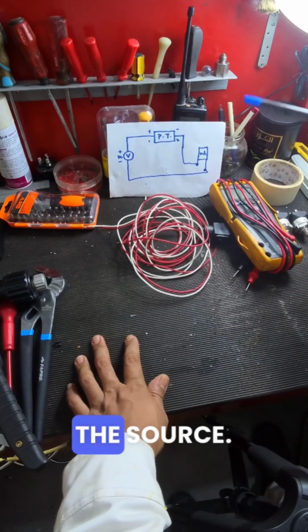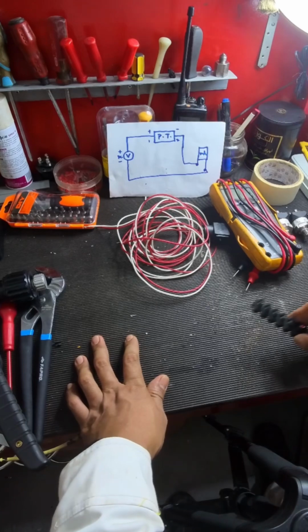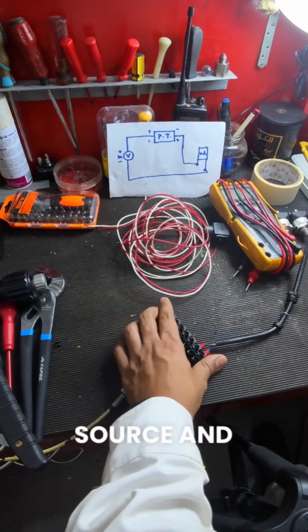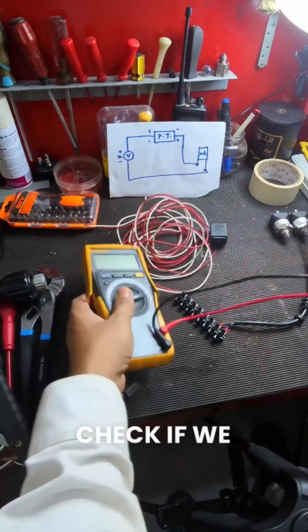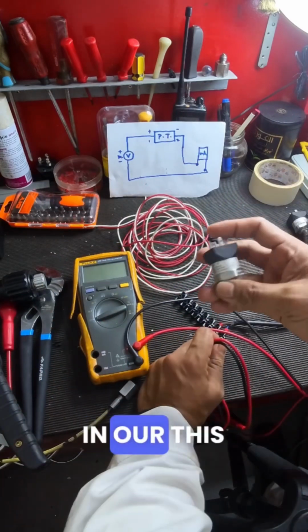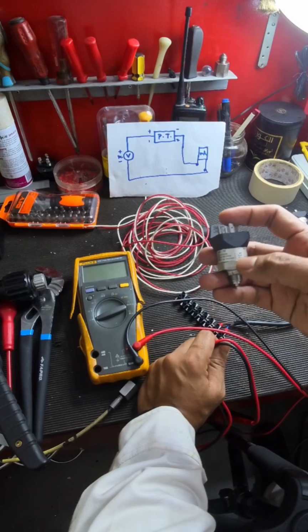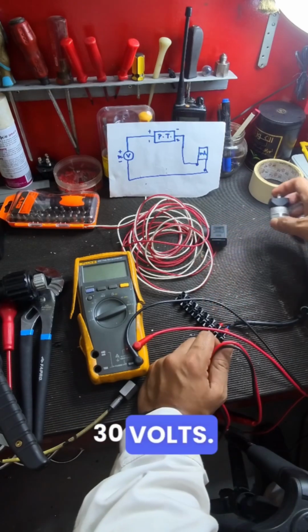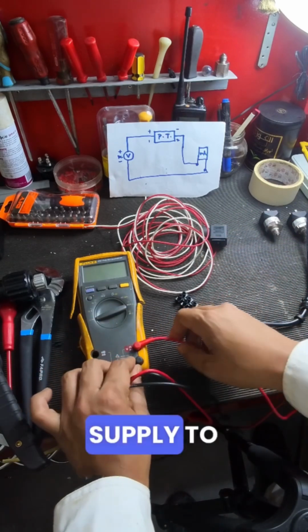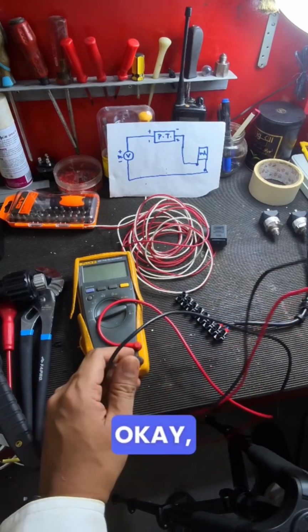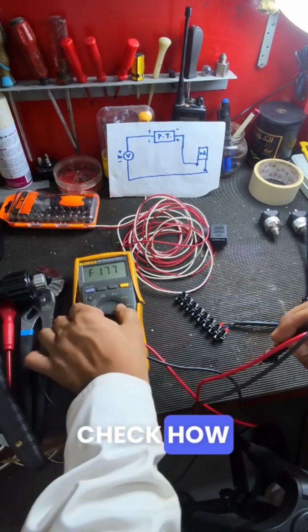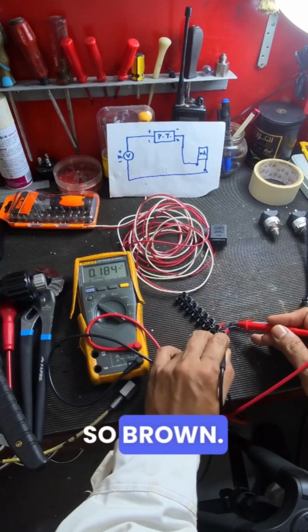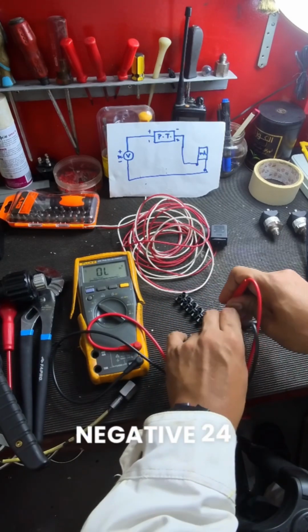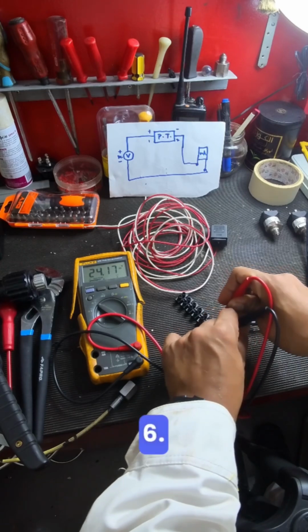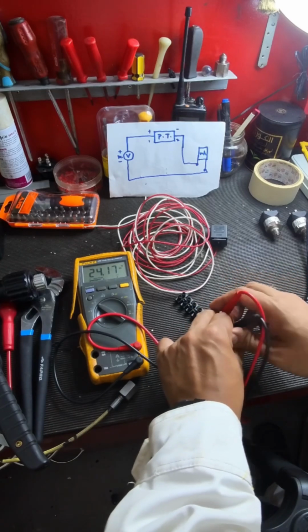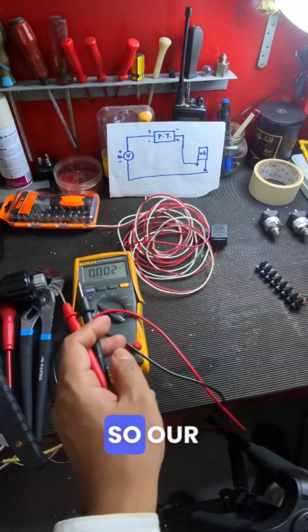So let's follow that. Let's have the source. This is the power source, and we have to check if we have power supply. As per our pressure transmitter, we have a source range of 8 to 30 volts. I have already set our power supply the same as our system. Let's check the power source that we have. Brown is positive, blue is negative. 24.6. Okay, so the power supply is good.